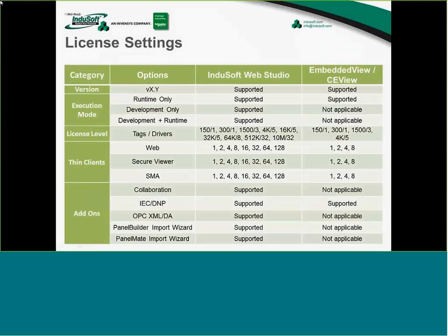And one thing that's interesting on this is you don't have to install any license on your client side. So if you access from the browser, we will install the plugin for you. Of course, you have to run the browser for the first time as an admin, so we have the rights to install our plugin. Or you can get from the bin folder the thin client setup, and then you get your web client running. You connect, you don't have to install a license on your client. The license goes on the server along with your hard key or soft key. So if you have to update to support more clients, you don't have to do anything on the client stations. You just update the server, and you don't have to do anything on the client side. The client doesn't require a license for itself.